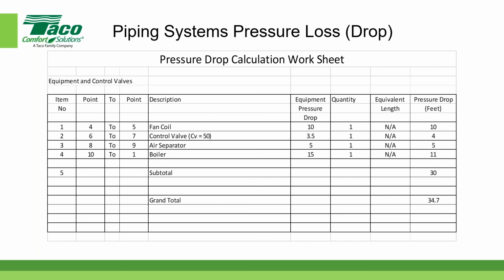And as I said a moment ago, in this little simplified example, let's assume that it's a constant flow. It's not in reality, but let's assume it was. Then I would want to have a maximum velocity of 8 feet per second. If it was a variable flow system, I would probably design the piping system at a higher velocity allowance of maybe around 10 feet per second, knowing that the maximum flow in gallons per minute is probably only 1 or 2% of the time. And the majority of the time, the velocity is going to be less than 10 feet per second. And so I can conserve on pipe size when it comes to that approach.